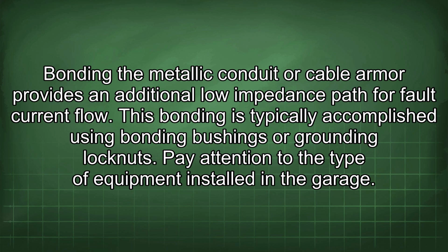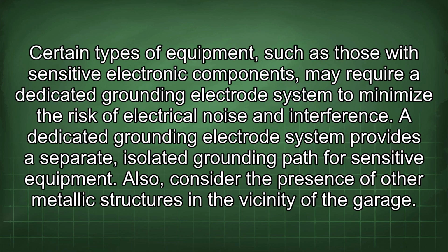This bonding is typically accomplished using bonding bushings or grounding lock nuts. Pay attention to the type of equipment installed in the garage. Certain types of equipment, such as those with sensitive electronic components, may require a dedicated grounding electrode system to minimize the risk of electrical noise and interference. A dedicated grounding electrode system provides a separate, isolated grounding path for sensitive equipment.